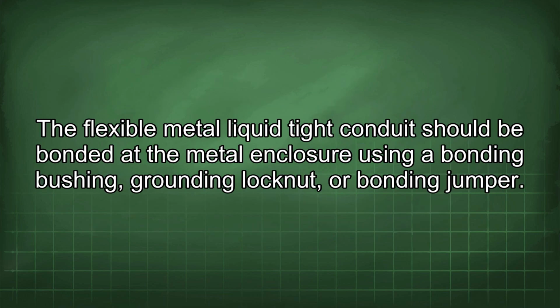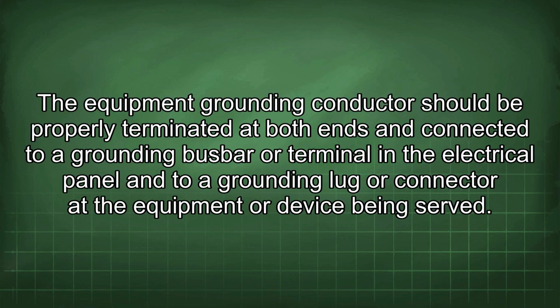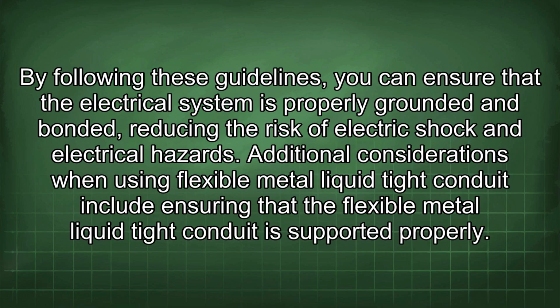The flexible metal liquid tight conduit should be bonded at the metal enclosure using a bonding bushing, grounding lock nut, or bonding jumper. The equipment grounding conductor should be properly terminated at both ends and connected to a grounding busbar or terminal in the electrical panel and to a grounding lug or connector on the equipment or device being served. By following these guidelines, you can ensure that the electrical system is properly grounded and bonded, reducing the risk of electric shock and electrical hazards.